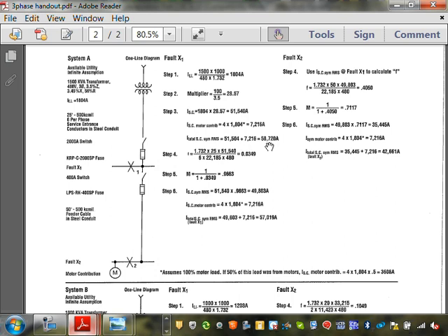Divide it to find the M factor. F factor is F for fault. Divide it to find the M factor. And from the M factor, you multiply it by the short circuit right at this point, not here. That will give you the contribution of the motors, and the contribution at this point. So right at this point, look at that. We knocked down the short circuit, guys. We started with 58. Because of the impedance, we knocked it down to 42, just by the impedance of the cables. Just one impedance by cables.